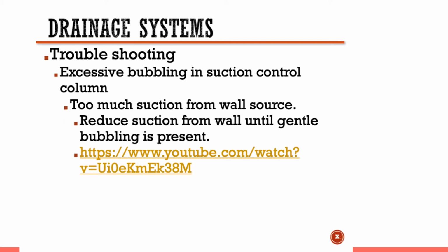Again, excessive bubbling could mean you have too much suction from the wall source, so you want to reduce it until you have gentle bubbling. A little YouTube video on that.